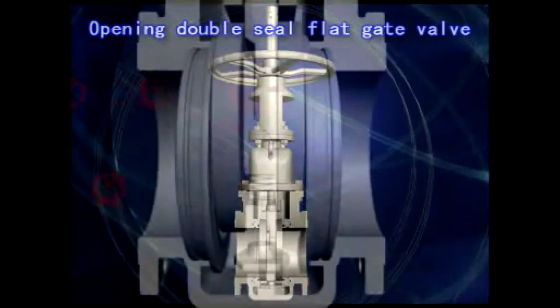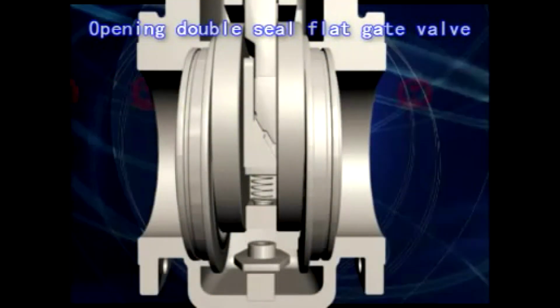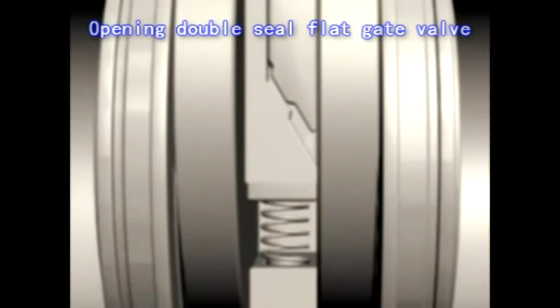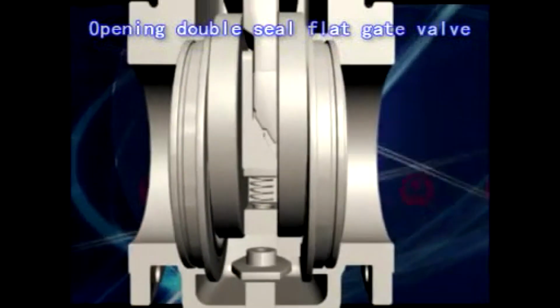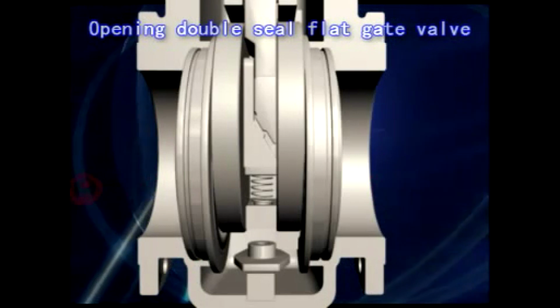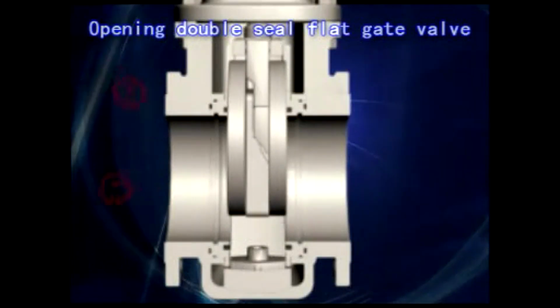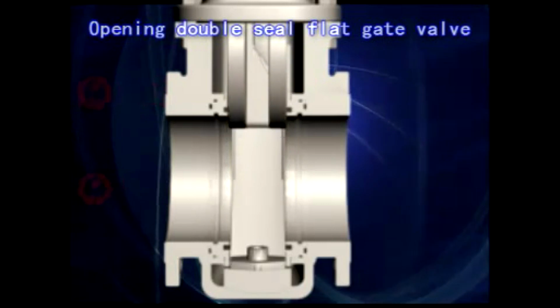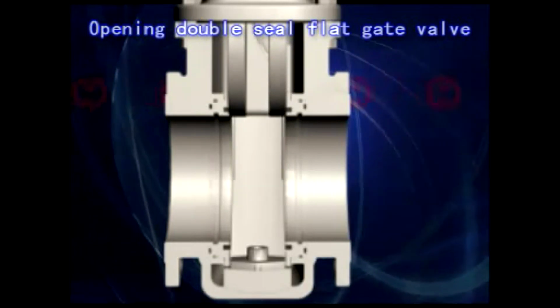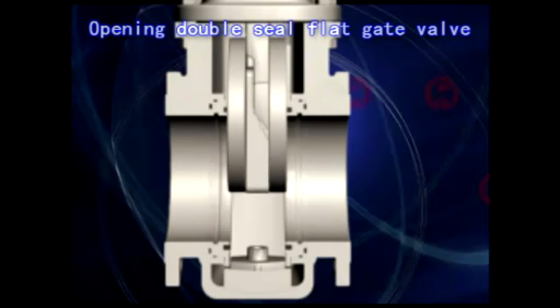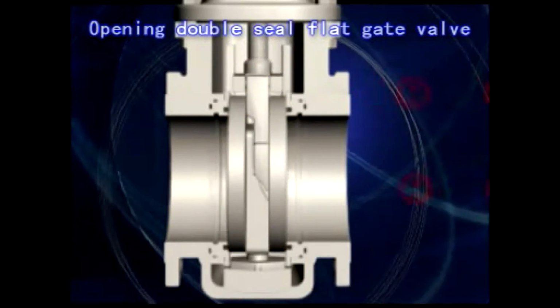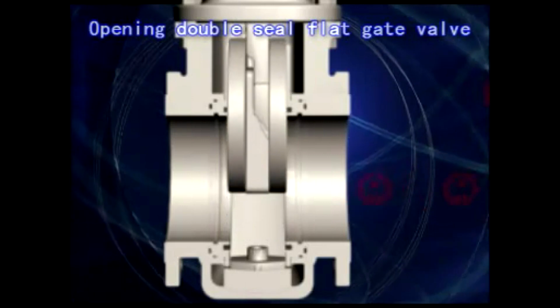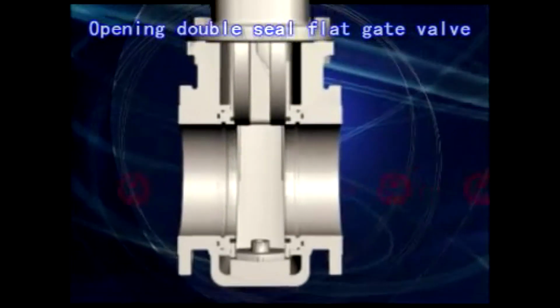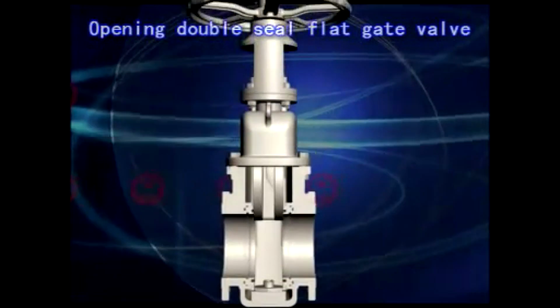3. When the valve is closed, the up and down wedge blocks will slide against each other to open two sides of the disc and press the seat sealing face. 4. Dual seal structure, with sealing face inlaid with reinforced composite material. Initial seal is reinforced composite material to metal seal. When the valve keeps closing, the disc will elastically compress the reinforced composite material, thus forming a metal-to-metal seal between disc and seat sealing face, so as to greatly improve the sealing reliability of the valve.